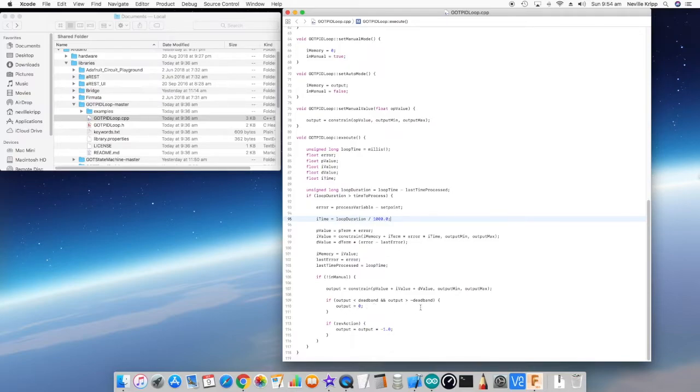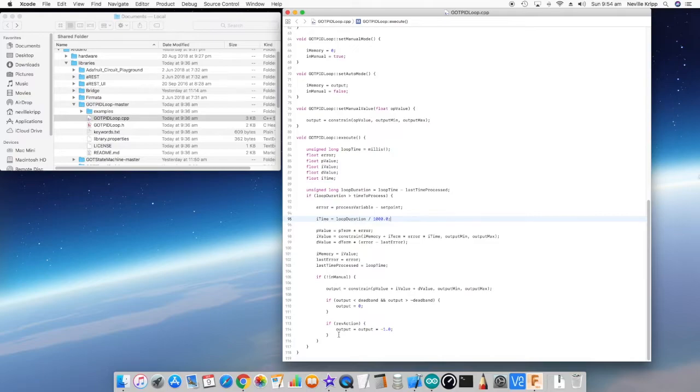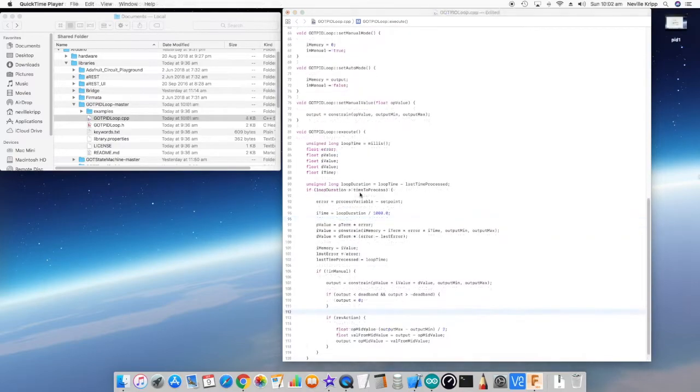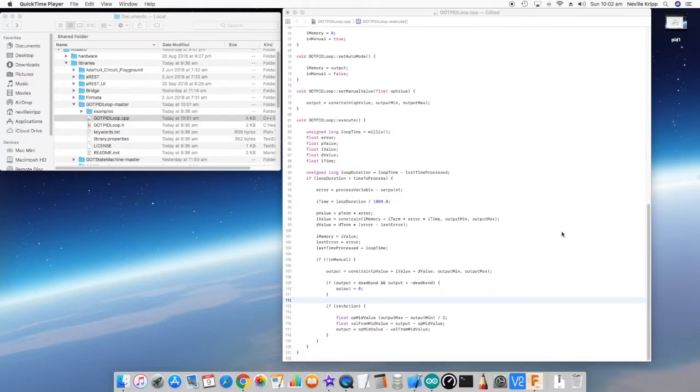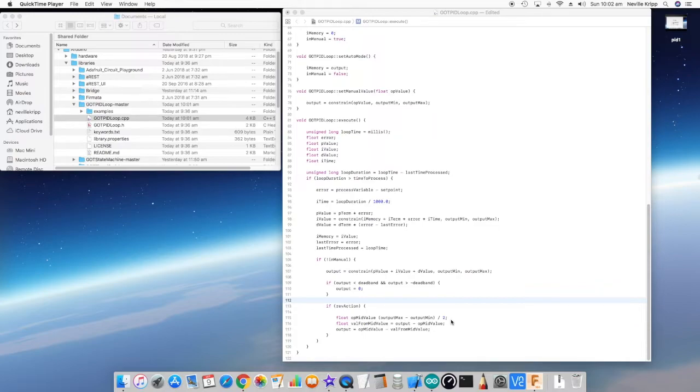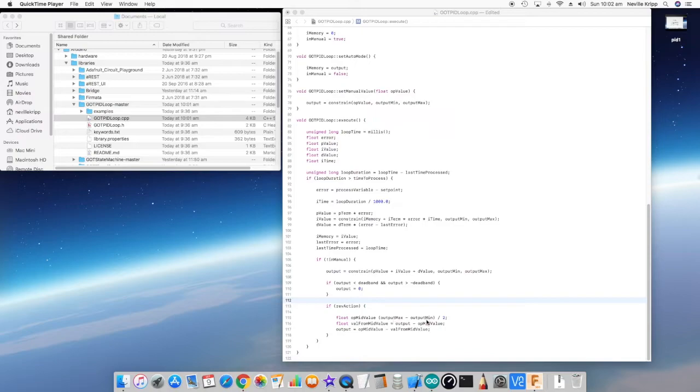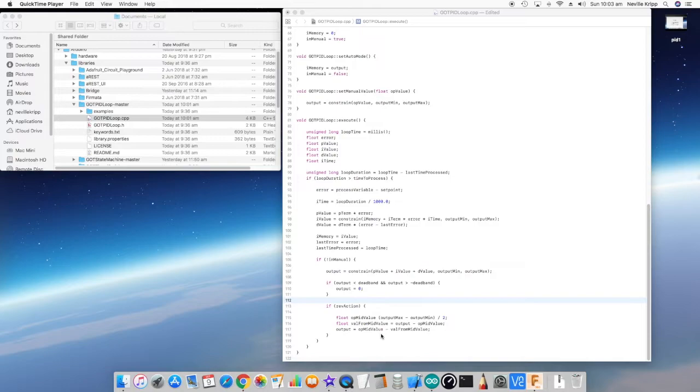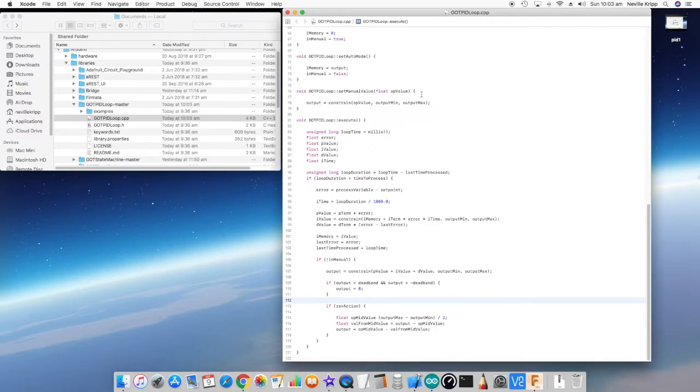Then we look at the action of the actual control loop. After a quick little fix, if we look at the reverse action now, if it is reverse action, then what we need to do is apply the difference between the output and the mid value in the other direction. So that's what we're doing here—calculating the mid value dependent on the output limits, and then seeing where the output is in relation to that mid value, and then applying it in the opposite direction to the mid value. So that's the execute method complete.